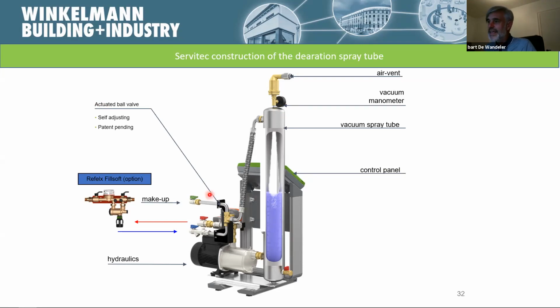So this is the technology behind our degassing system, and as you can see, it's all self-adjusting. That means if we don't reach that good negative point, this valve and our software will always make sure that we get those deep degassings, reaching the maximum negative vacuum point of our running pump.